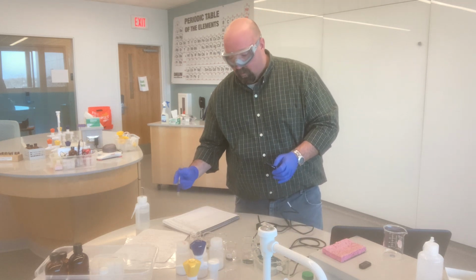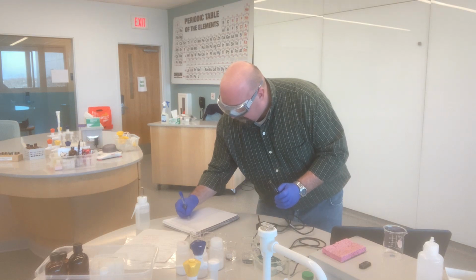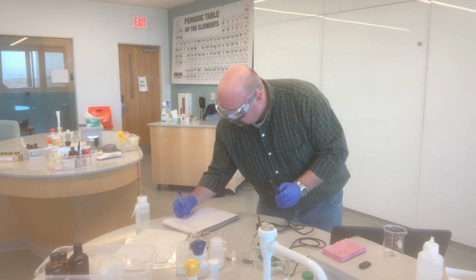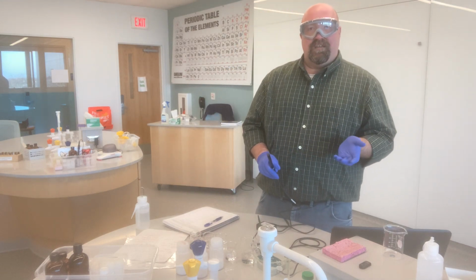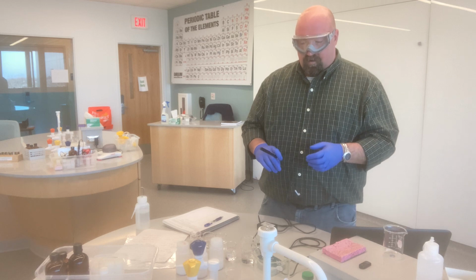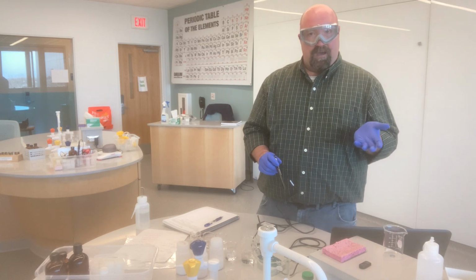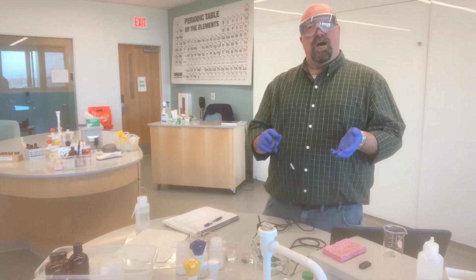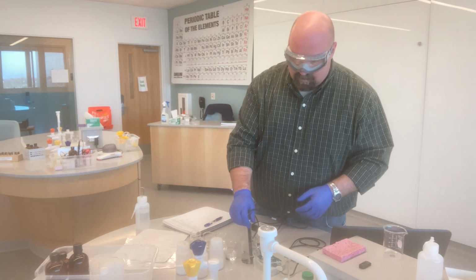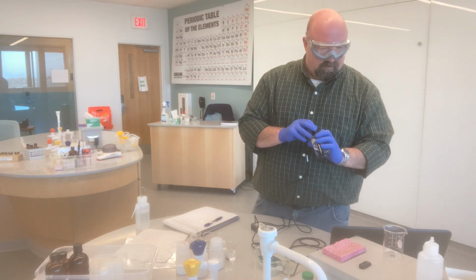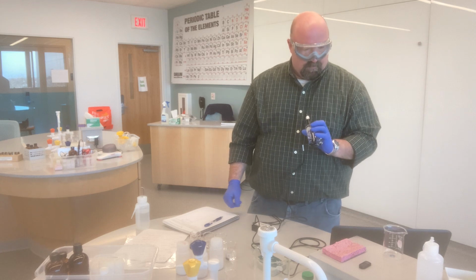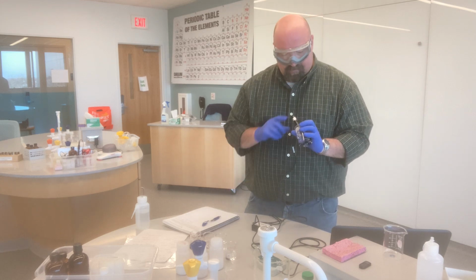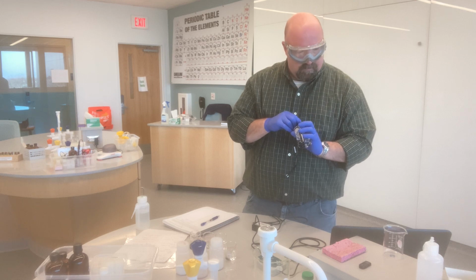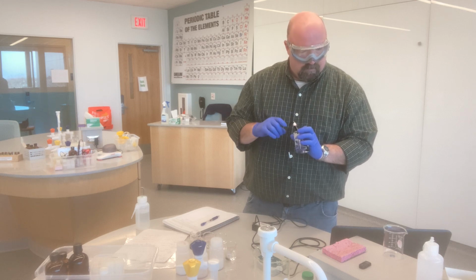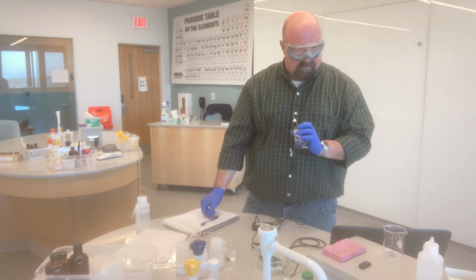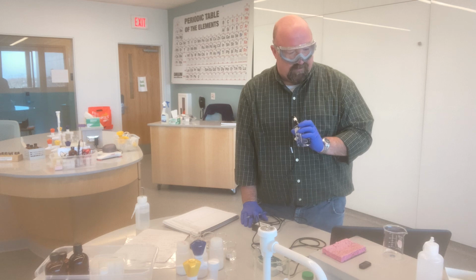And so the first one that I'm going to start with is the 0.025 molar NH4NO3. We always like to get measurements in triplicate whenever we can. So what I'm going to do is stick my probe down in, let it stabilize, get my measurement, take it out, rinse it off, and put it back in. I'll do that for a total of 3 measurements so we can get our triplicate measurements. And again, all this data will be provided for you, but I will shout out the numbers as I am getting them as well. Conductivity does tend to jump around a little bit, so I watch until it's fairly stable.